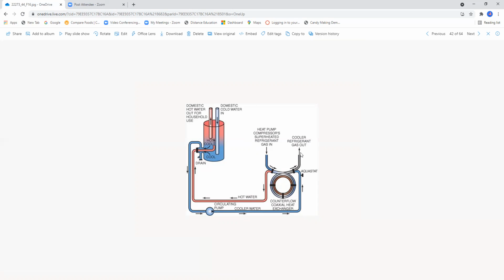Now, the problem is this compressor doesn't run continuously. You could have periods where the hot water is hot and periods where the water is not so hot, unless this tank is very well insulated and you have sufficient hot water volume inside this tank for the drawdown to work. So if you're taking a Hollywood shower, which is a long version of a Navy shower, if you're taking a long shower in your house utilizing this concept, you will deplete the water here very quickly. And natural gas, of course, has the ability to heat the water very quickly. Whereas if you're using waste heat from the compressor, it's a continuous heat source as long as the compressor is running. If it's not running all the time, you might have problems.